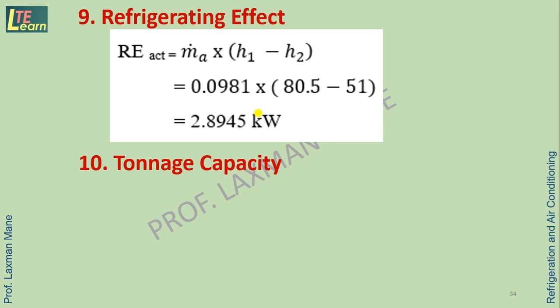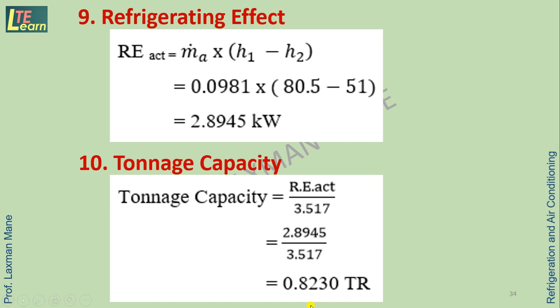Tonnage capacity is given in TR, so this kilowatt we convert. This is the conversion factor: refrigerating effect in kilowatt divided by 3.517. So we find the value of tonnage capacity in TR.